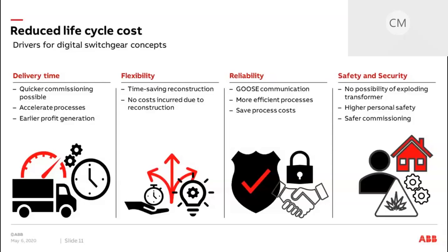So in addition, the need for configuration in hardware wiring is minimized, and changes can be applied later just in the software logic. This also results in reduced time spent on installation and commissioning activities on site due to less interpanel wiring and fewer components to be tested in the low voltage compartment. That means while speeding up the delivery of the switchgear and the installation and commissioning process, you can also generate profit earlier with your data center.